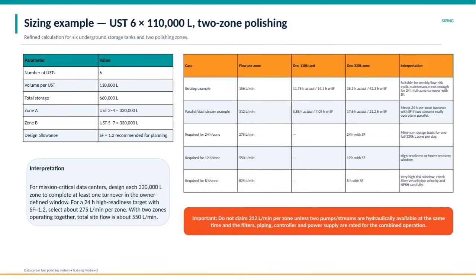Here we have a detailed sizing example for underground storage tanks and polishing zones at a data center fuel polishing system. The setup includes 6 underground storage tanks, each holding 110,000 liters, split into 2 zones. Zone A with tanks 2 to 4 and Zone B with tanks 5 to 7, each totaling 330,000 liters. The design incorporates a safety factor of 1.2 to ensure adequate planning and reliability.